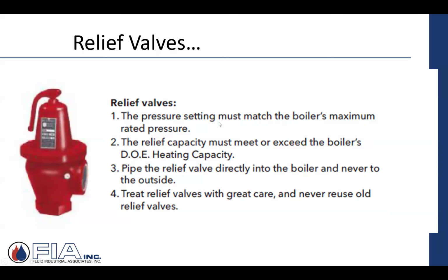So one is the pressure setting. It has to match, in this case, a boiler. It could be a boiler, could be whatever that appliance is, could be a heat exchanger, but whatever that heat source's maximum rated operating pressure is. So that's one number that it needs to meet. The other part, which is just as important, is the relief capacity, what it can discharge, what it can get rid of, what it can relieve, hence the name relief valve. It has to meet or ideally exceed the heating capacity of that heat source, a boiler typically, a heat exchanger, a water heater.